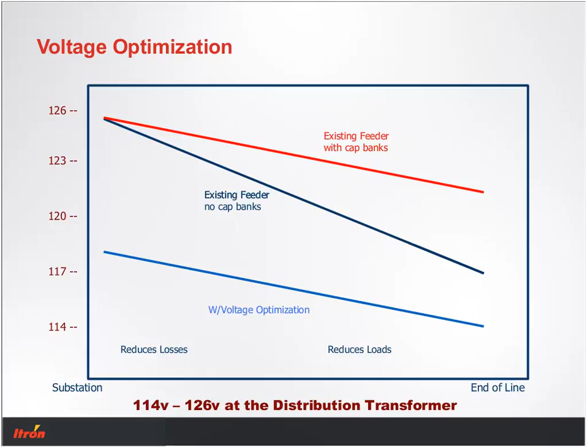So in Pullman, the engine, or the brain, if you will, is a distribution management system. And this distribution management system is using real-time power flow calculations. Now, a key thing about that is that for the real-time power flow calculation to be accurate, it needs meter data or load data at points on the feeder so that the allocation of load is appropriately done such that the accuracy for voltage calculations is correct.